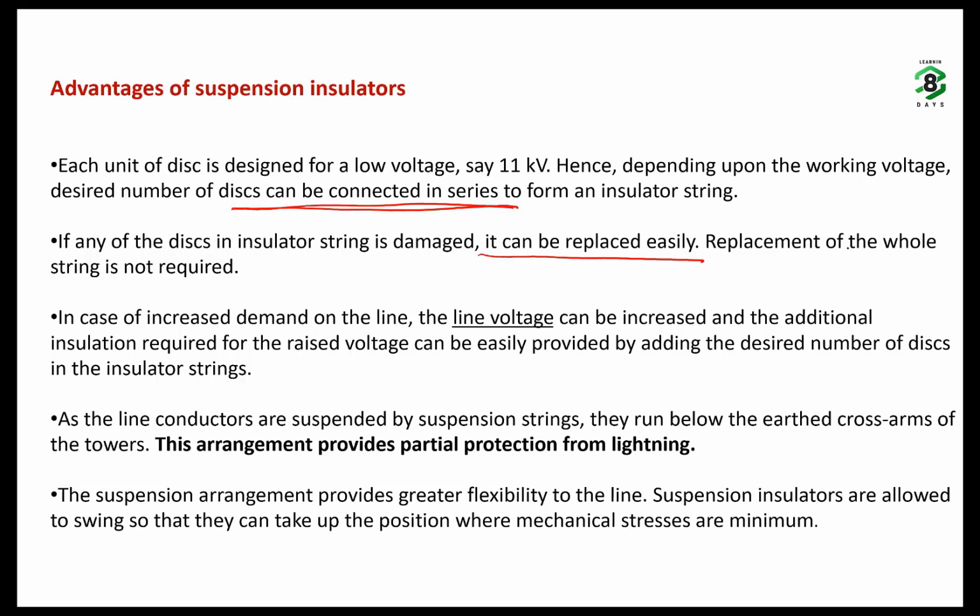Okay. In case of an increase in demand, the line voltage can be increased, and the additional insulation required for the raised voltage can be easily provided by adding the desired number of disks in series with the insulator strings. Okay. As the line conductors are suspended by suspension strings, they run below the earthed cross arm of the tower. This arrangement provides partial protection from lightning.